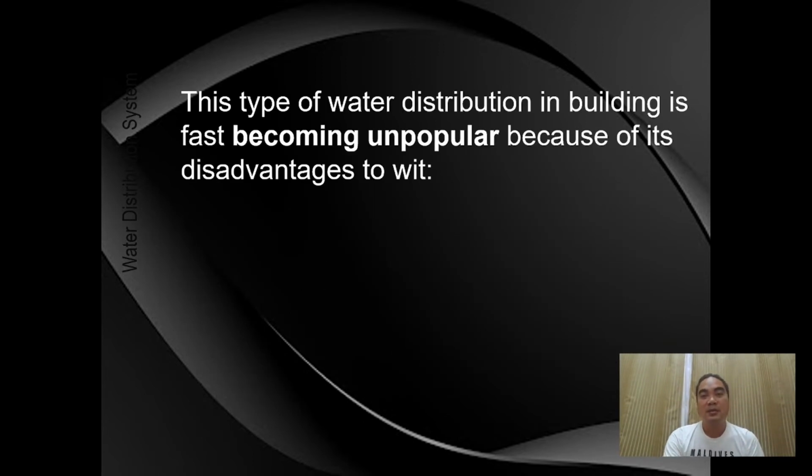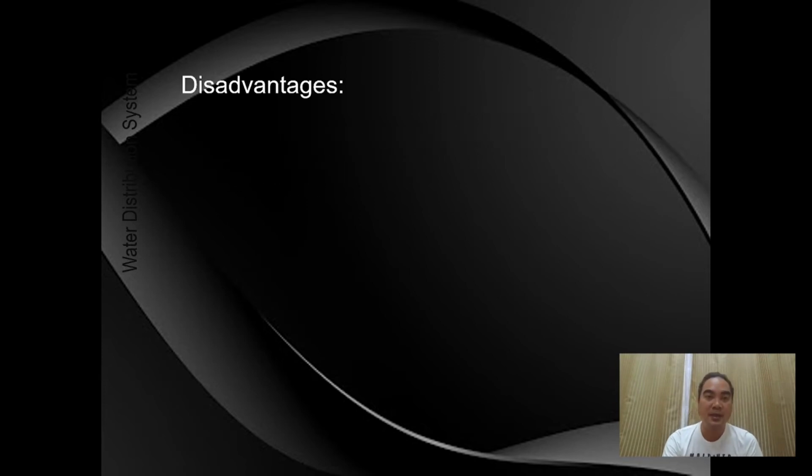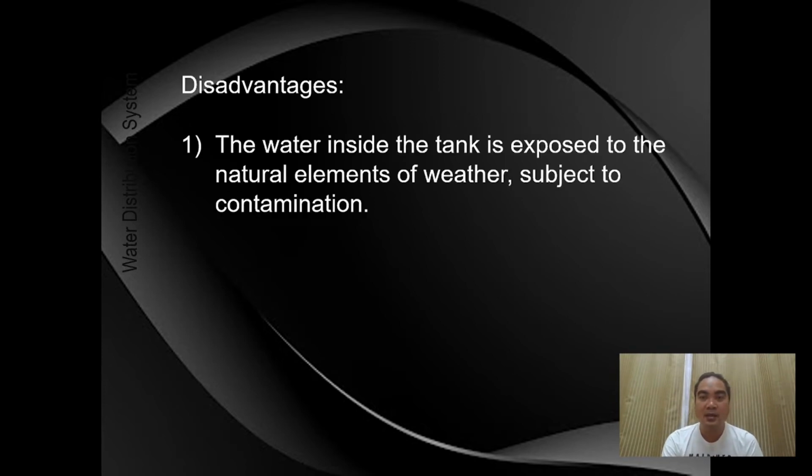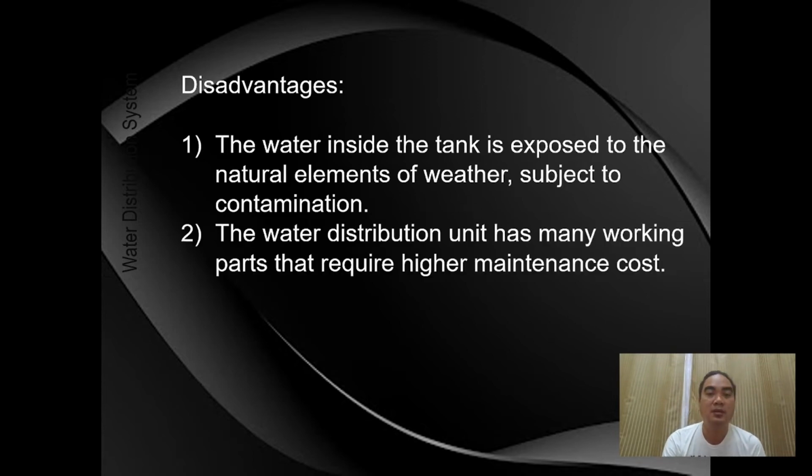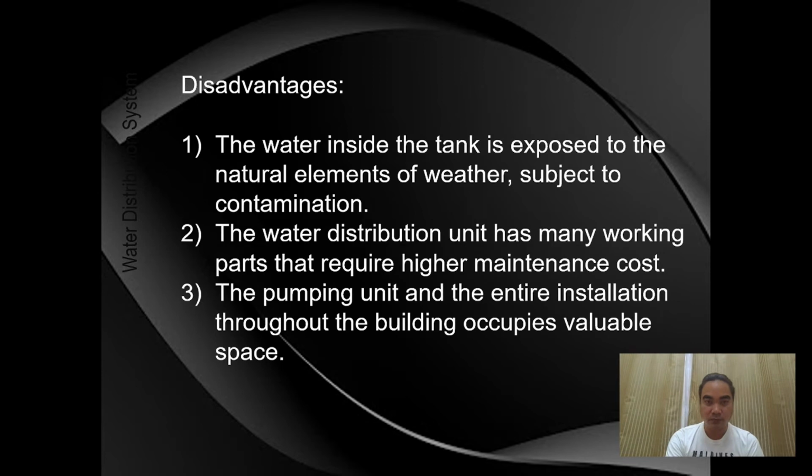This type of water distribution in buildings is fast becoming unpopular because of its disadvantages also. May mga disadvantage din siya. Okay? Disadvantage: the water inside the tank is exposed to the natural elements of weather, such as contamination. The water distribution unit has many working parts that require higher maintenance costs. The pumping unit and the entire installation throughout the building occupy valuable spaces.